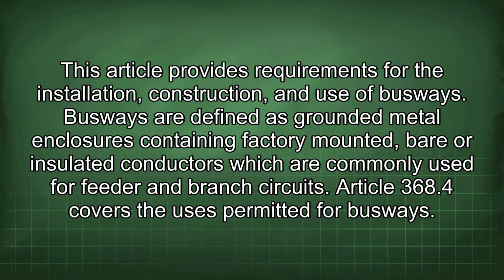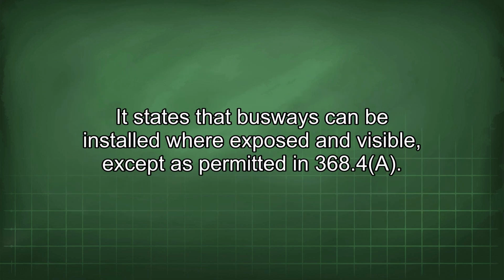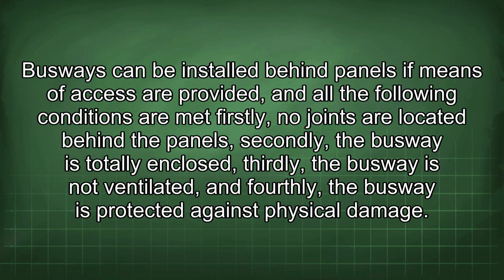Busways are defined as grounded metal enclosures containing factory-mounted, bare or insulated conductors which are commonly used for feeder and branch circuits. Article 368.4 covers the uses permitted for busways. It states that busways can be installed where exposed and visible, except as permitted in 368.4a. Busways can be installed behind panels if means of access are provided, and all the following conditions are met.